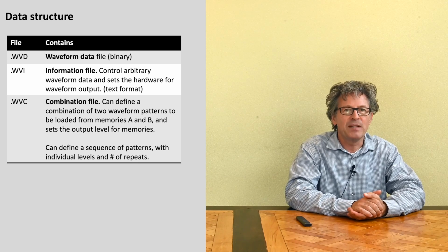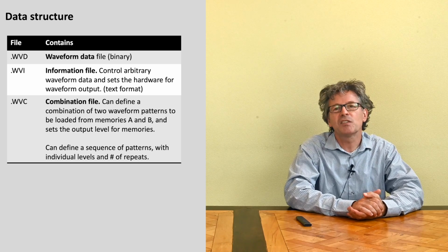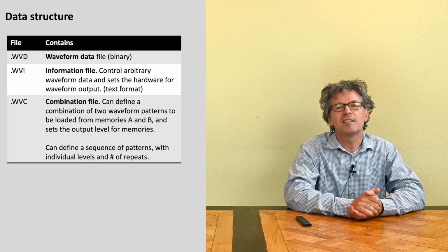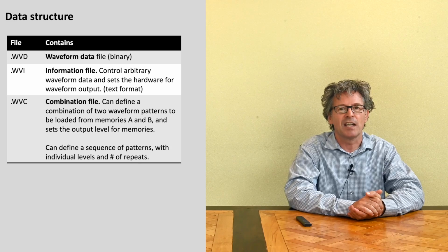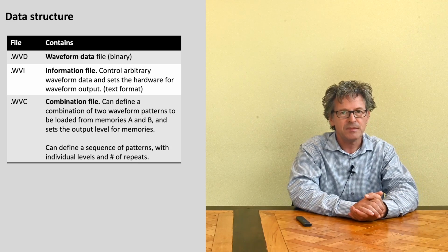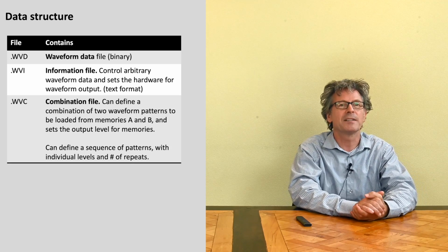There is the waveform information file, and that contains additional information about the whole settings of the device around the waveform. So like the sample frequency for which the file was designed, some output level and other relevant stuff. It's a readable file in text format.